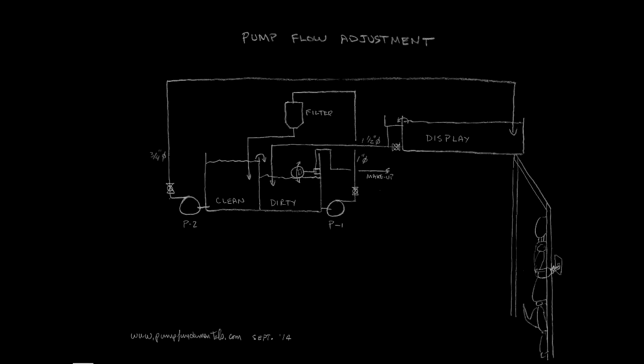The pumps you buy will no doubt have a larger capacity — more head and flow — than your calculations determine. It's better to have a bit more capacity than a bit less. Therefore, you will want to control the flow out of each pump to provide the flows you require to the different parts of the system. A ball valve on the discharge of each pump will help you achieve that.